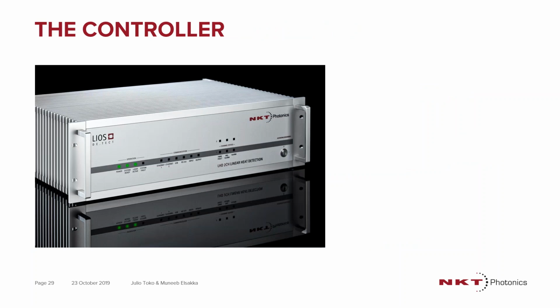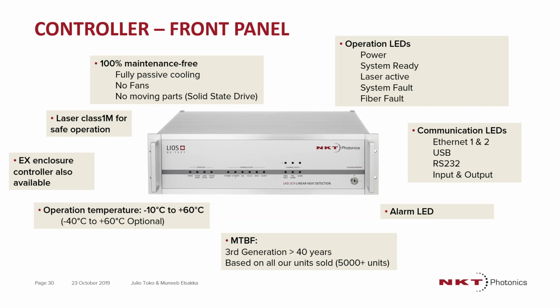Now we'll talk a little bit more about the controller, which is the brain of the system. Most fiber optic linear detection now has to go with the code. So in the case of most of these controllers, you have to have operating LEDs that can tell you whether the system is on, the system is ready, whether there is a fault, or there is an alarm or a pre-alarm. So we go with a design with a front panel that can tell you exactly what's going on with the system. This is very similar to, and goes with, the requirements for fire protection panels and such.